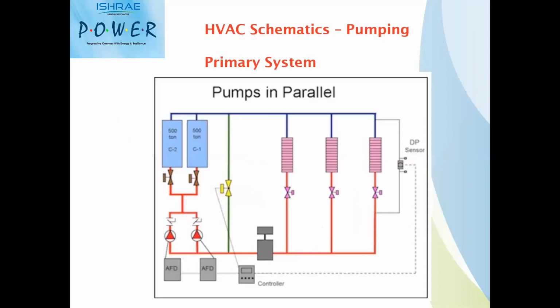So this is typically a primary system where this is your load, this is your chiller, and only the primary pumps are installed. There are no secondary pumps. So this primary will circulate the water from pumps to the loads, and the return water is coming back to the primary, where there are no other secondary pumps associated with this scheme. And there will be, of course, cooling tower pumps if it's a water-cooled chiller.